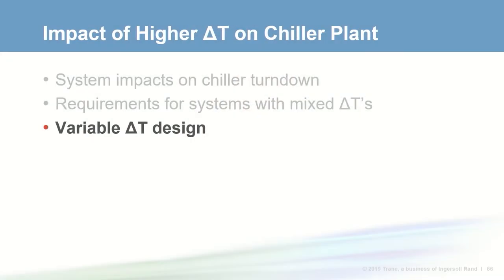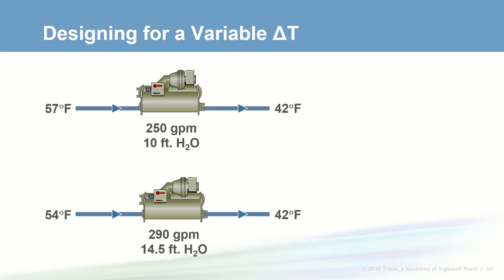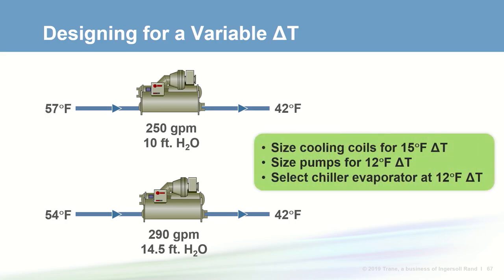The last topic is designing for a variable delta T. If you have a mixture of two-way and three-way valves, want to over-pump a chiller in a VPF system, or plan on doing chilled water reset, any of these can result in less than design delta T during operation. One approach: take a design chiller selected for 250 GPM at 10 feet of pressure drop, and if you ran it at design tonnage with a 12 degree delta T instead of 15, you'd get 290 GPM at 14.5 feet of pressure drop. You'd still size coils for 15 degree delta T, but use the 290 GPM and increased evaporator pressure drop to ensure you have enough pump to handle a variable delta T design.